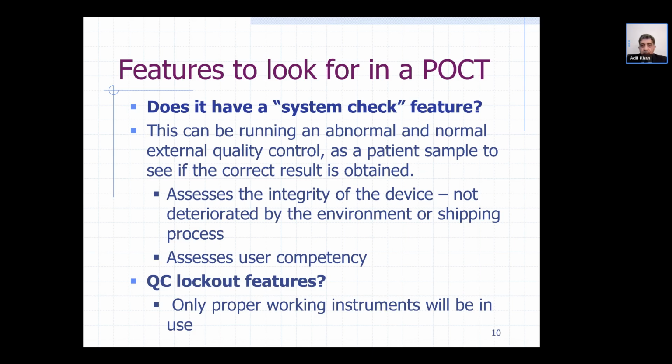This can be like running an abnormal or a normal quality control. You can run that, and that assesses the integrity of the device. If it's a lateral flow device, it makes sure that all the capillary channels are functioning correctly. The reagents are working according to the manufacturer's expected recommendations, and it also tests the user's competency on how to perform the test, because when you run a quality control, you're going through the same process as you would with a patient sample.